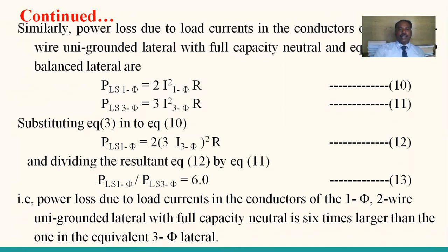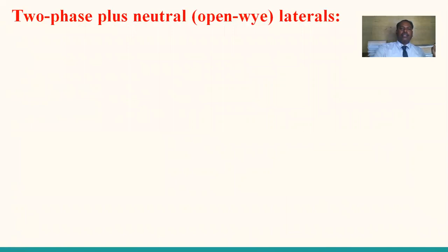Yes. So this is the criterion where the single phase 2-wire uni-grounded lateral can be converted into a 3-phase 3-wire balanced system. Both the voltage drop as well as the power loss increase by 6 times. Yes. So it is not an efficient system. So therefore, the system cannot be preferable for power transmission from the substation to the load centers. And this is also another kind of system in the non 3-phase lines.